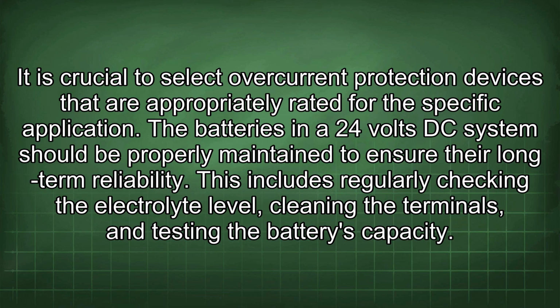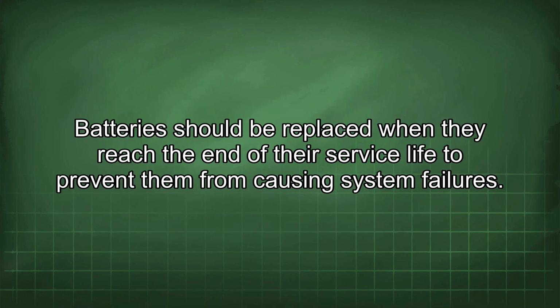The batteries in a 24 volts DC system should be properly maintained to ensure their long-term reliability. This includes regularly checking the electrolyte level, cleaning the terminals, and testing the battery's capacity. Batteries should be replaced when they reach the end of their service life to prevent them from causing system failures.